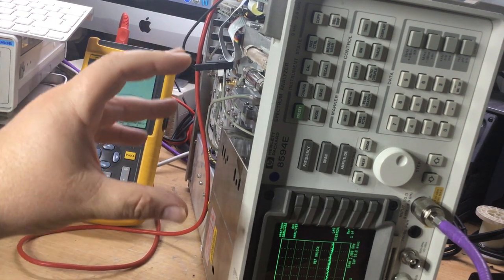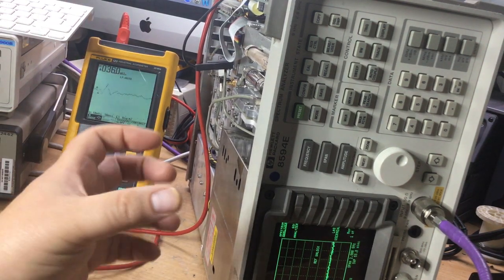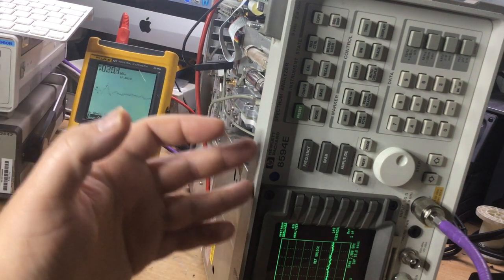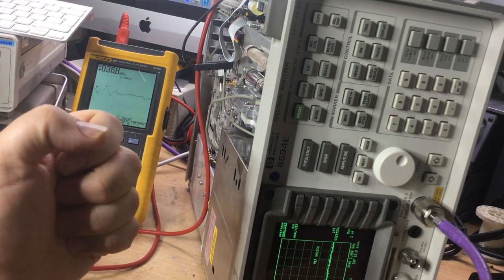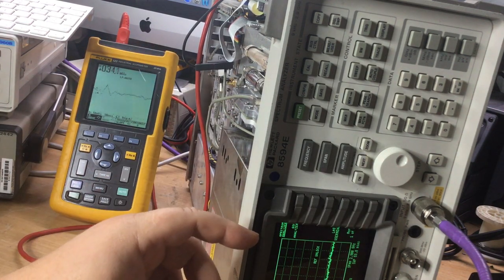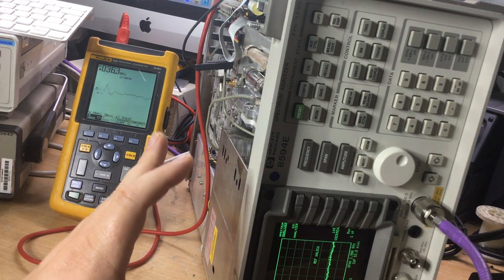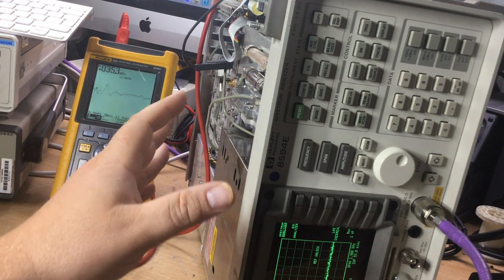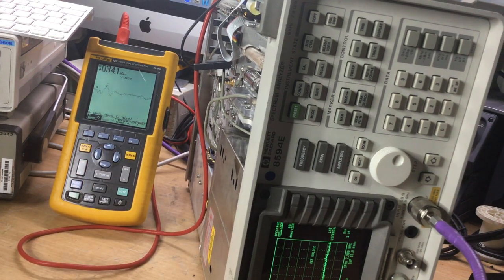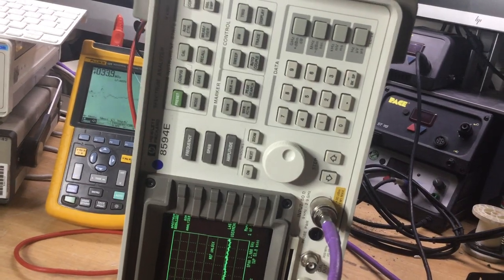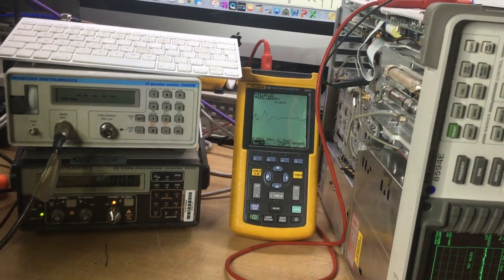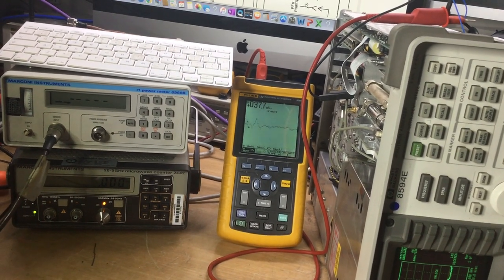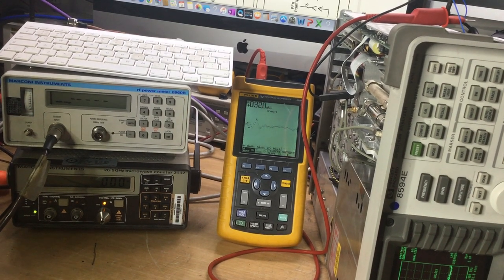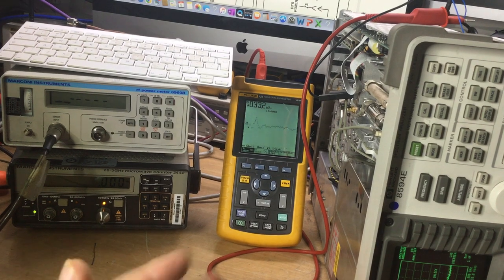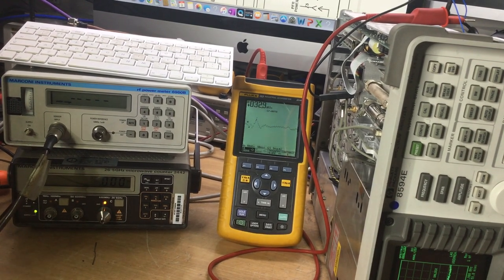They've got the track gen on them, they are totally different modules inside, a lot more compact. You can tell those spectrum analyzers because when you pick them up, they're a lot heavier to carry. They weigh two to three times what this one does, even though it's in the same casing. So I have spares for the higher level model spectrum analyzers, but not for the basic low cost spectrum analyzer, which this particular model is. So it's unfortunate really, that I think we've hit the buffers when it comes to dealing with the fault.